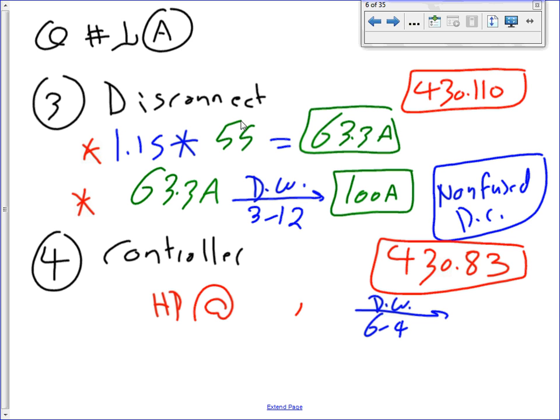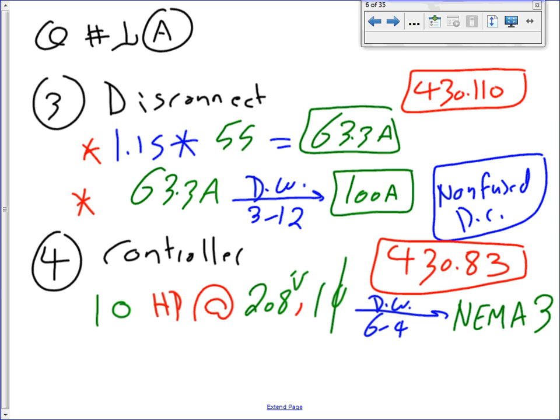Controller. The way we size the controller, guys, you take the 10 horsepower, in this case, at the voltage that we have, which is 208 volt, single phase, and the catalog will give you NEMA 3, NEMA 3. When you go there, make sure you go to 208 volt, or it says also 240 single phase. I want you guys to get the catalog. This will help you know which column to go under.